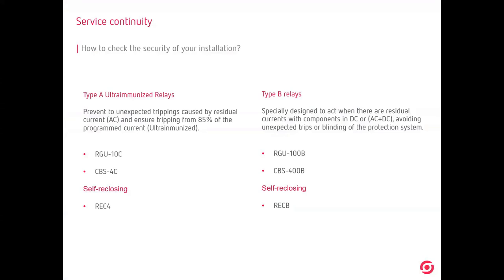Type B is for DC loads or DC plus AC, okay? Later on, I will show you one slide talking a little bit more about that. Ultra-immunized, also take care about that. Our Type A relays are ultra-immunized. It means that the tripping level starts at 85%, and if tripping, obviously at 100%, okay?